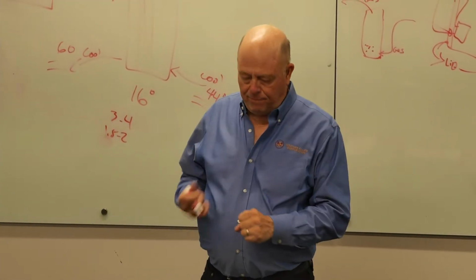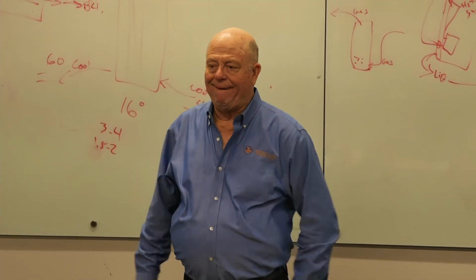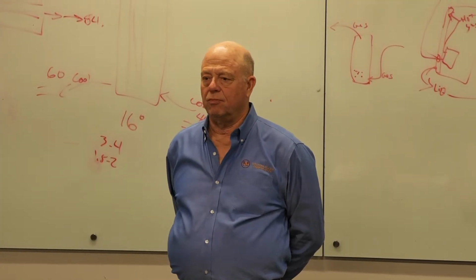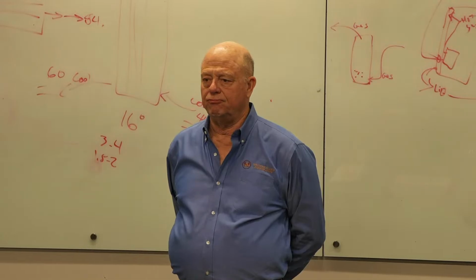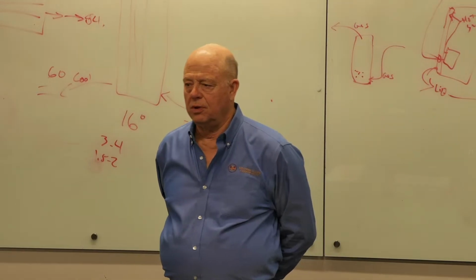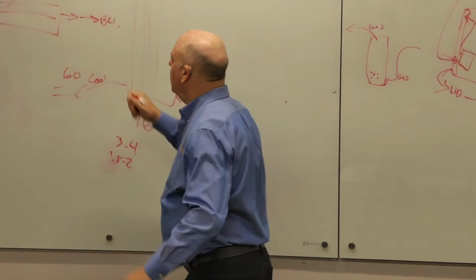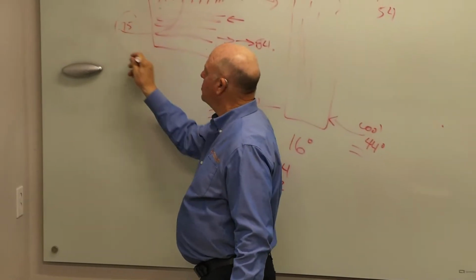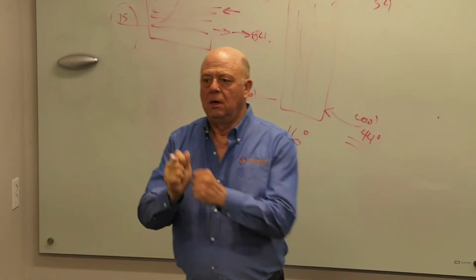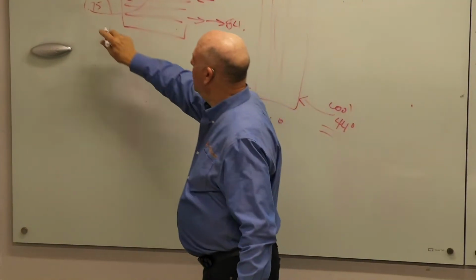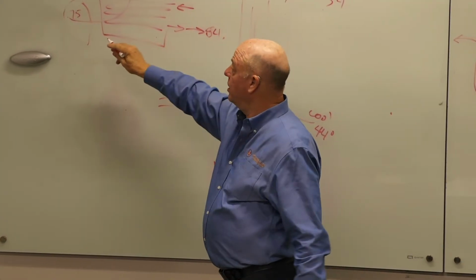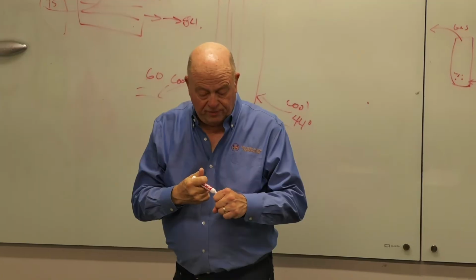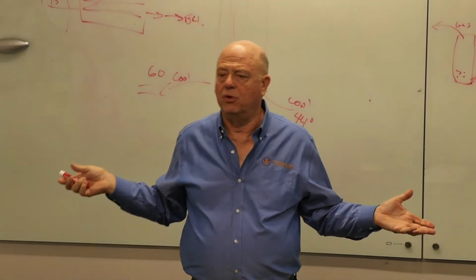In this one, it's the outside temperature and the going out temperature, not the coming in temperature and the outgoing temperature? Correct. The driver is the wet bulb. Oh, the wet bulb, okay. And the approach on this cooling tower. Okay, yeah, on a cooling tower. Okay, got it. The same is true if it's any kind of evaporative cooling device.